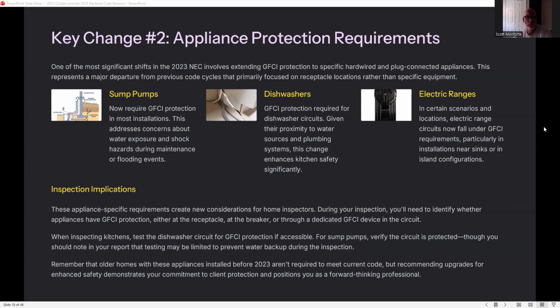Dishwashers: GFCI protection is required for dishwasher circuits, given their proximity to water sources and plumbing systems. This change enhances kitchen safety significantly. Electric ranges: in certain scenarios and locations, electric range circuits now fall under GFCI requirements, particularly in installations near sinks or island configurations. Inspection implications.